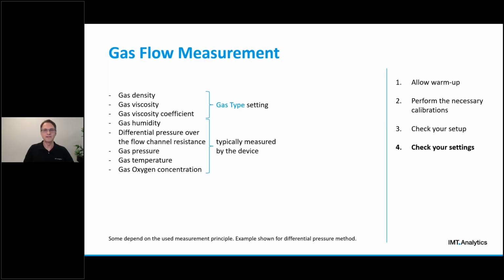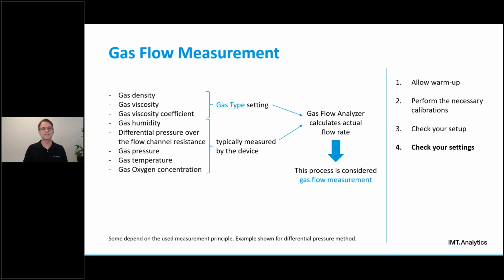The other parameters are typically measured by the gas flow analyzer, for example, gas temperature, the gas pressure, and the oxygen concentration. So with all these set and measured values, the gas flow analyzer can then calculate the actual flow rate of gas passing through the device. And we call this process gas flow measurement.